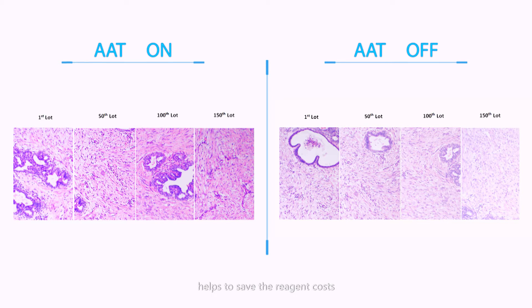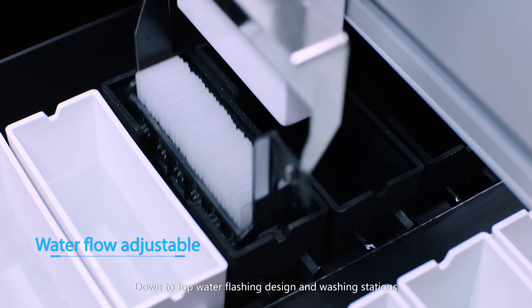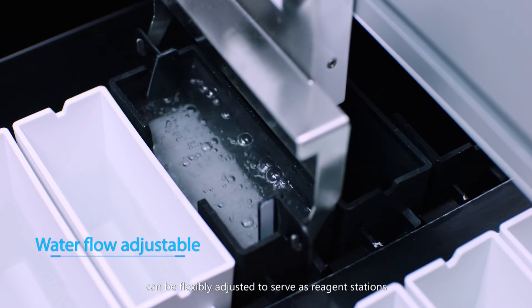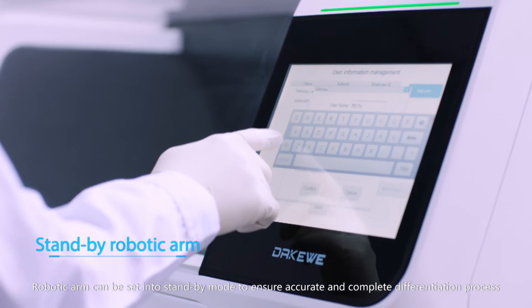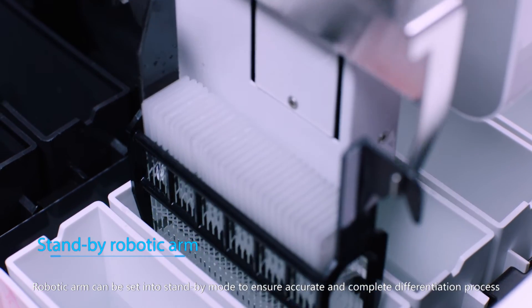Down-to-top water flushing design and washing stations can be flexibly adjusted to serve as reagent stations. The robotic arm can be set into standby mode to ensure accurate and complete differentiation process.